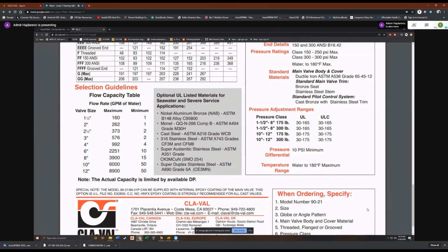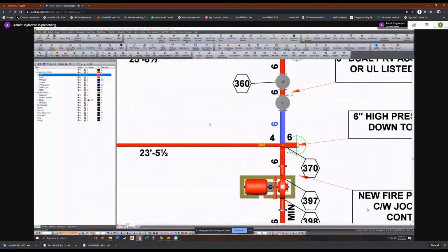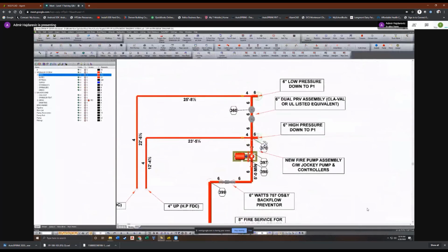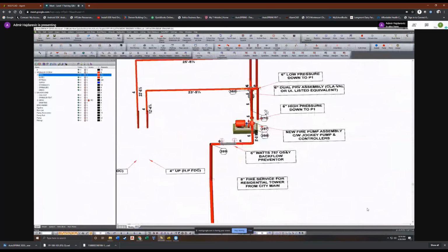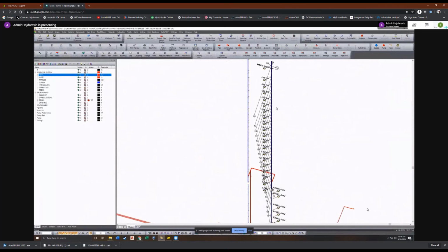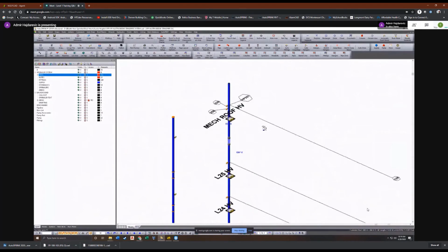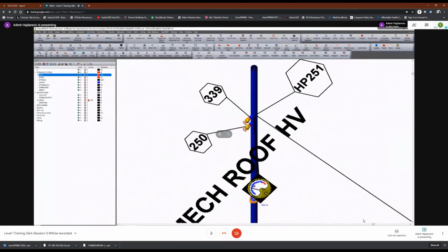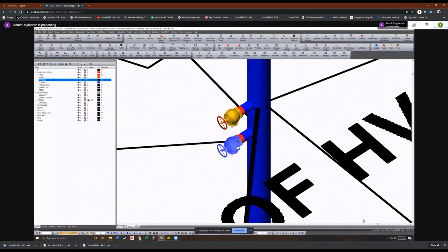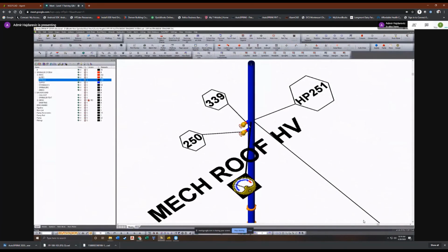And the program does have the ability to change the calculation method from demand to supply. So you do have the ability to run a supply calc to verify that downstream of this PRV, I'm only getting 150. The resistance that I've included is limiting downstream pressure to 150. And then the program will balance discharge and pressures based on what's available. I don't know if you necessarily need to go to that detail or not, but the option is there.